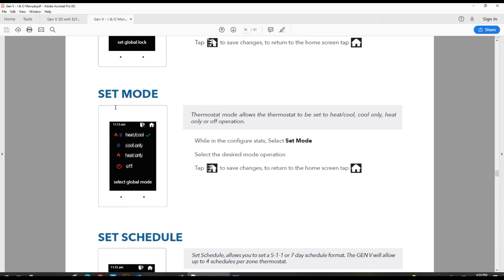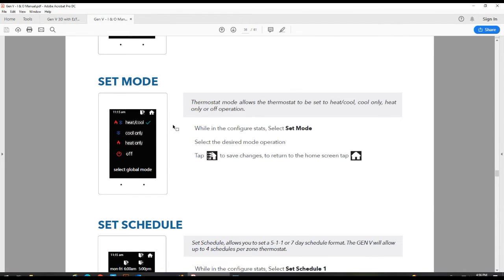You can also set your modes from the hub thermostat, for all your thermostats or individually. So if you're not sure how a thermostat is set up at any particular zone, because maybe you can't get to it, you can go in and check the modes and or change it according to the operation you would like.